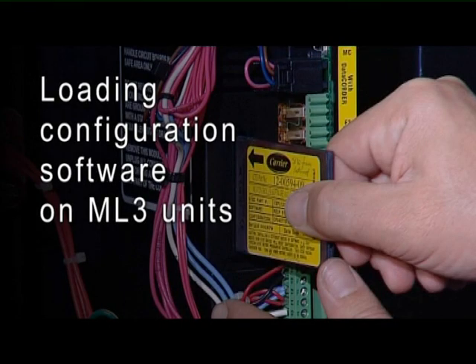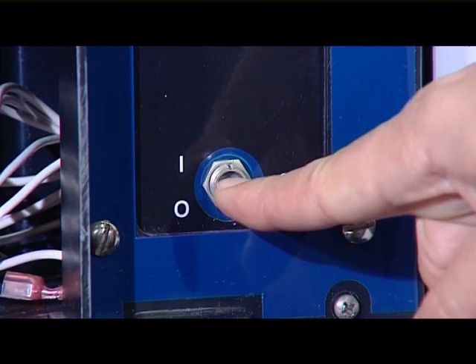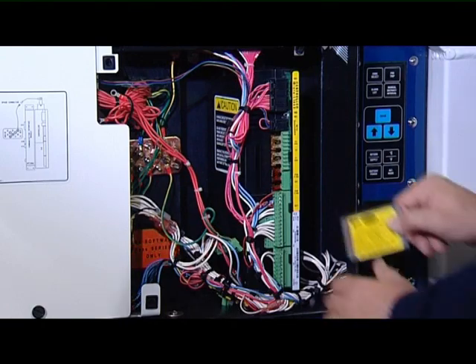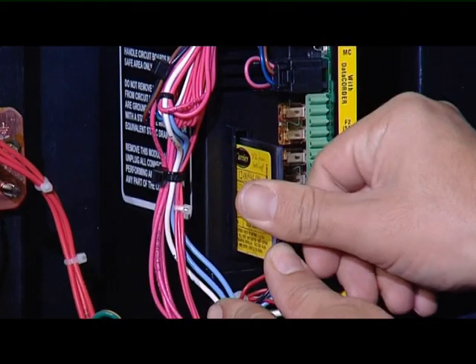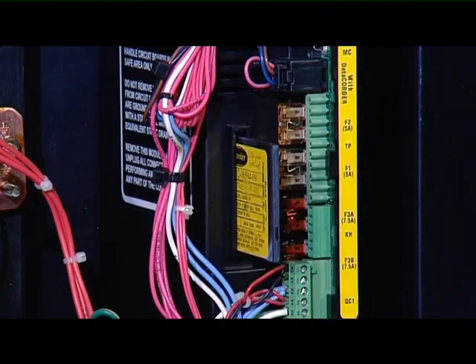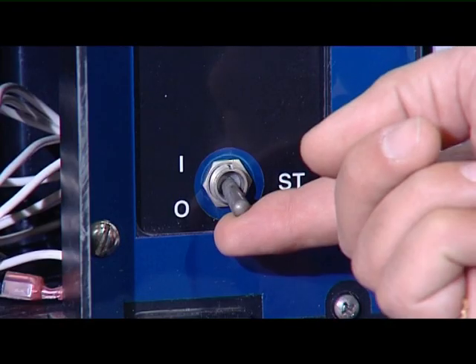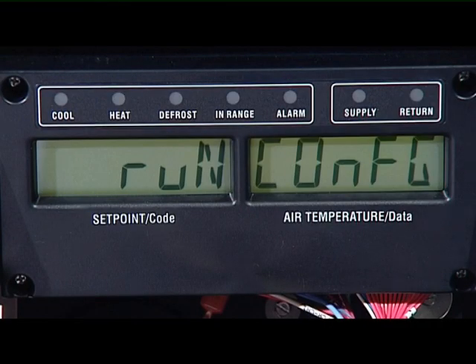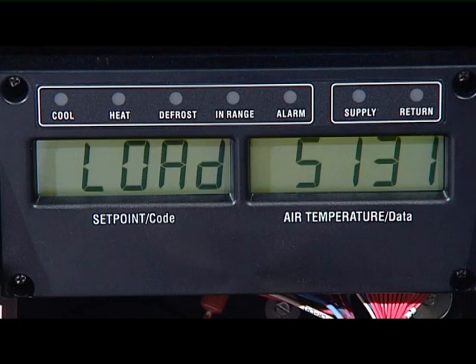Loading configuration software on Microlink 3 units. Switch off the unit. Insert the card. It's very important that the yellow label from the card should always face the condenser fan. Switch on the unit. The card contains the following files: configuration file, software number 5131.